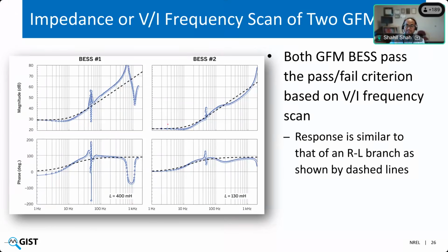And the last frequency scan test is V by I or impedance scan. So here you are seeing the impedance response of two grid forming BESS. The blue ones are the response measured using vendor-specific black box PSCAD models, and the dashed lines are the response of an RL reactor or RL branch, basically resistive at low frequency and inductive at high frequency. So we are comparing the positive sequence impedance response of two BESS with that of an RL branch. And from that, we can estimate what is the amount of inductance these two BESS are providing.